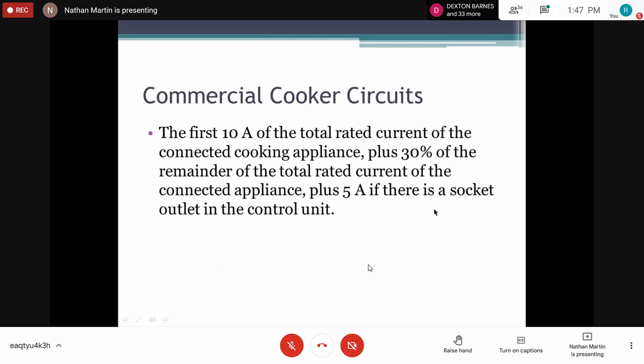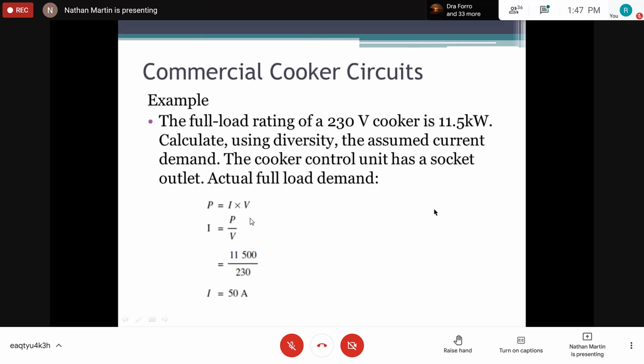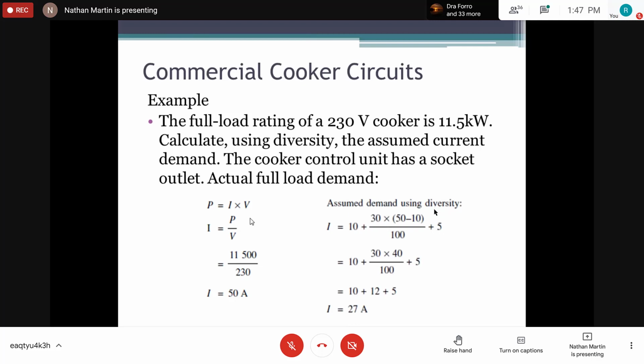Now again, realize: first 10 amp, right? Find 30% of the remainder, which is 30% of 40, and then add 5 amp if an outlet is being used, which it states that we must have, a switch outlet. Then we find our design current, which is 50 amp, right? And we know that at full load, this should be drawing 50 amp. So we say we'll find 10 amp, and then the remainder is 40 amp. We'll find 30% of that 40, add 5 amp to it, and then we end up with 27 amp.